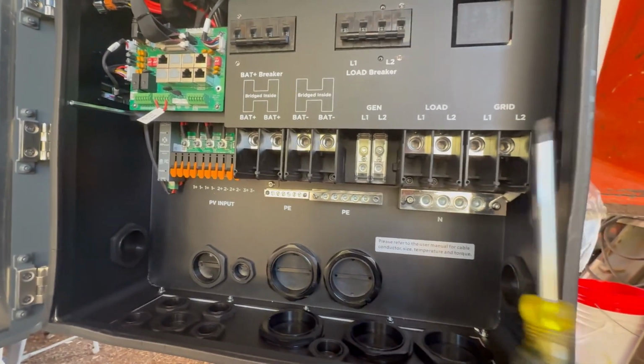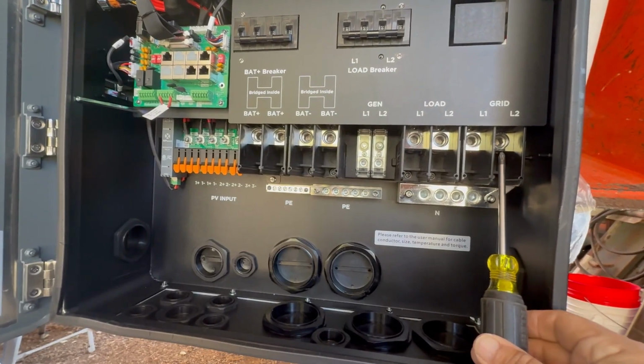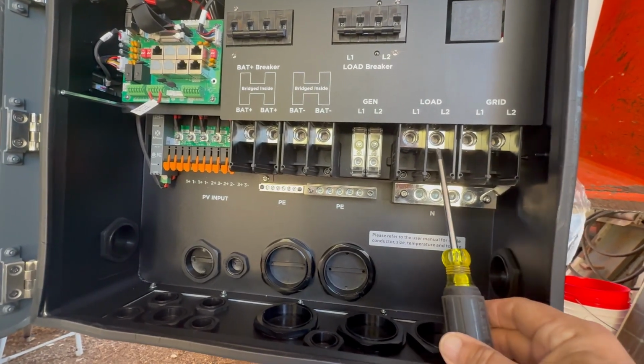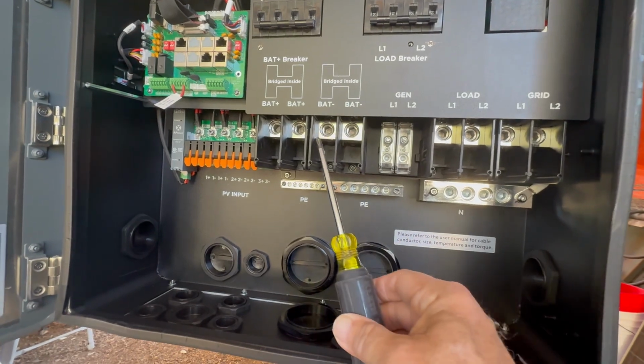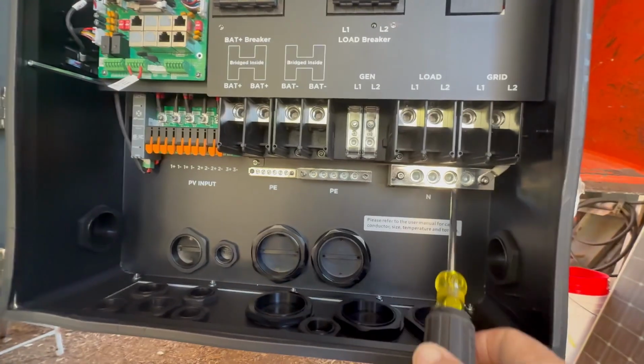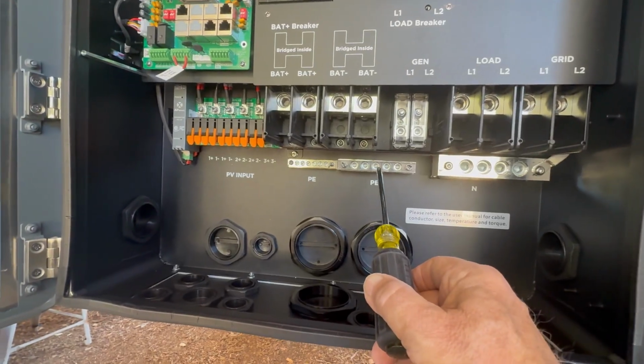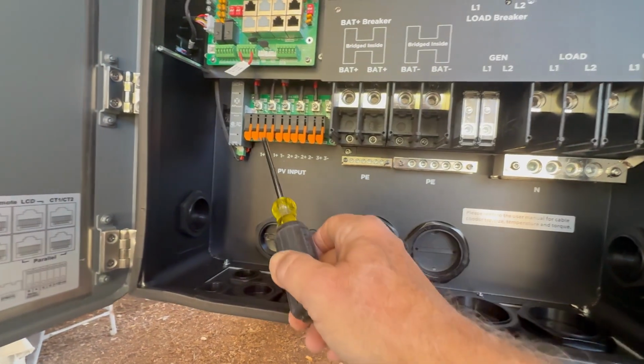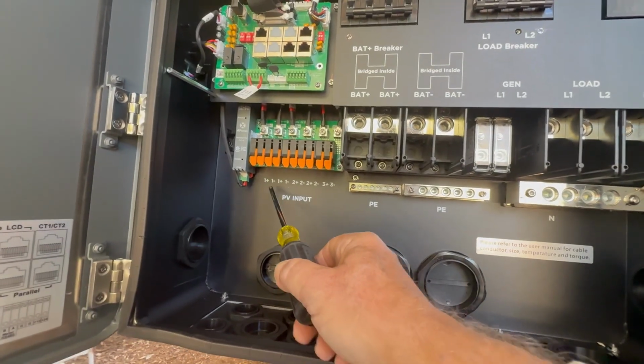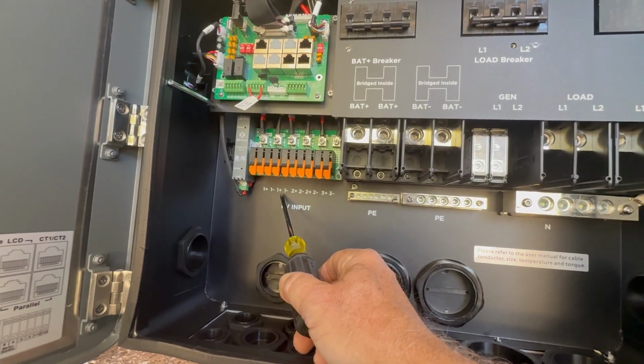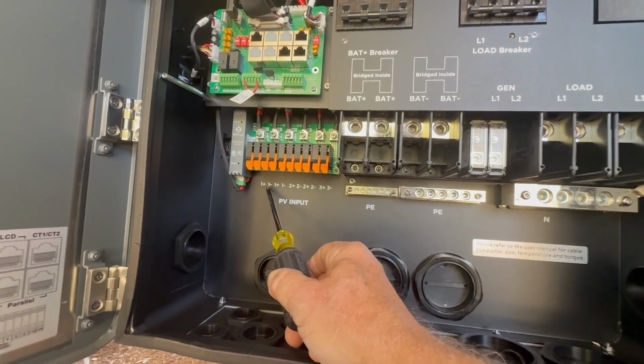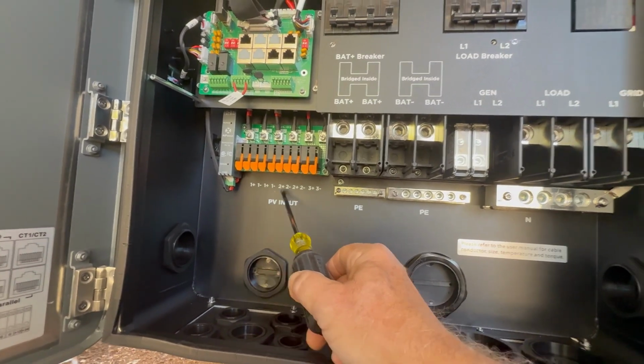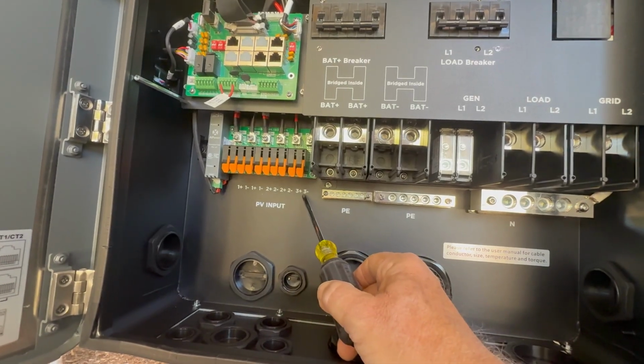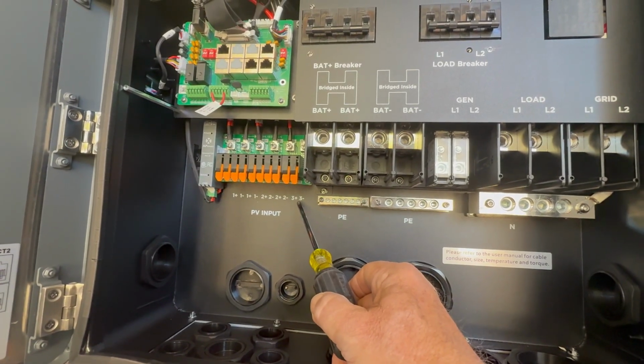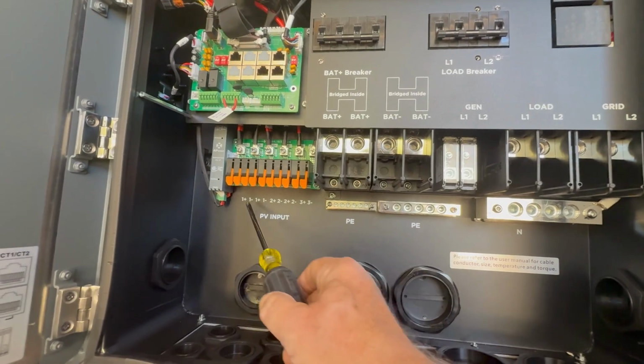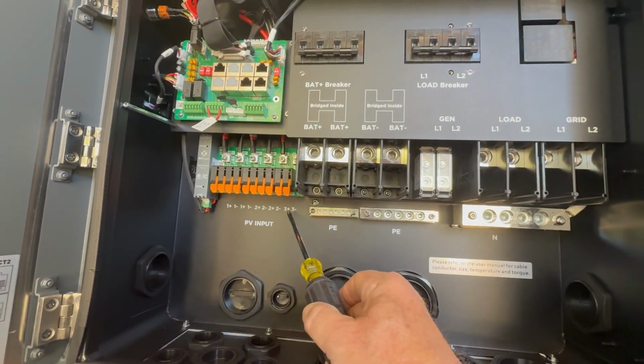Here's our layout. We've got our grid terminals, which accept up to 2 AWG I believe, a load terminal, generator terminal, and parallel battery terminals, a neutral bus bar, earth ground and a little baby earth ground. What I like is it now has 2 DC inputs for 2 identical solar arrays, plus a smaller regular one. I'll review the specs in a second about the maximum current coming in for each of these.